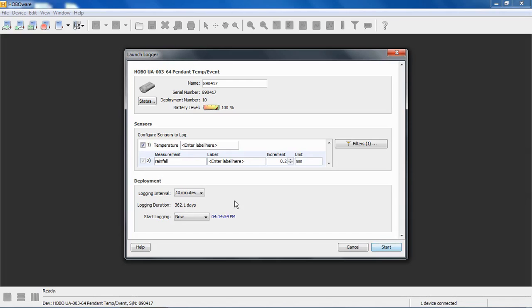It's not for the event channel. The event channel is scanning once a second. They're independent of each other. So with a 10 minute logging interval, you're not going to miss events in between those intervals because they log independently of each other.